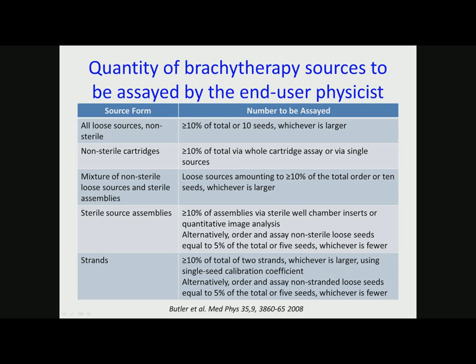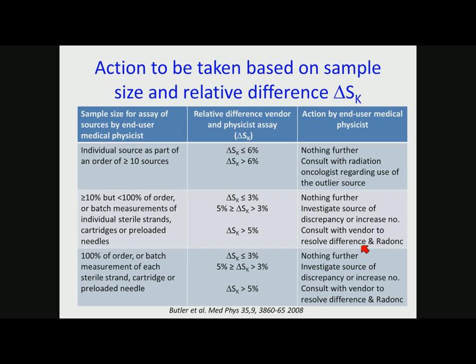If you're looking at individual seeds, usually if it's less than 6%, do nothing. If it's more than 6%, you can talk to the consulting radiation oncologist. If you're doing a batch of seeds, if you're doing 100%, if it's less than 3%, do nothing. Again, 3% is pretty good for random. These seeds are hard to make, and they have a short half-life. Like CS-131 has a 10-day half-life. So if you're a few hours off, your activity may be different. If you're between 3 and 5%, investigate the source of the discrepancy or increase the number of your QA. And if it's greater than 5%, talk to the vendor, see what the issue is. And usually the vendors are good. They'll call you and say, hey, there's a problem. And talk to the rad-onc and see if you want to change the treatment plan based on the activity that you found.